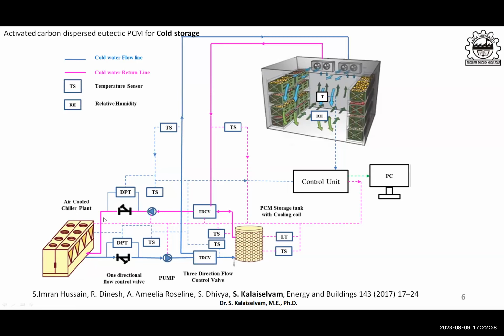But in case of the cold storage system with thermal energy storage system, there is an additional circuit. That circuit is nothing but a TESS, thermal energy storage system. This TESS will store the excess energy available in the chiller unit. During part load operations or part load hours, the excess cool energy—or sometimes heat energy—that is stored in this storage tank during part load hours can be used during peak load hours to maintain a proper temperature in the cold storage system.